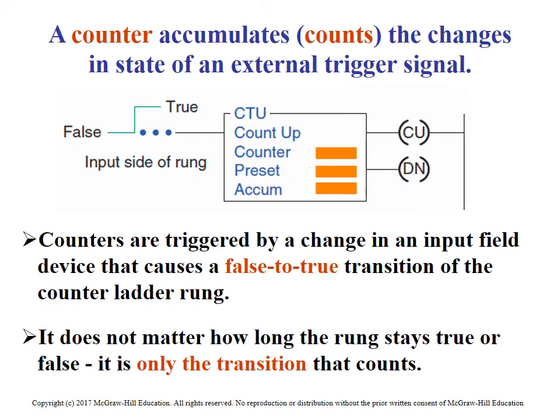As you remember in the previous segment, there are three components to the counters: there's the address, the preset value, and the cumulative value. It consumes three words — the control word, which has bits associated to it such as counter up, counter down, done bit, and all those. And then the preset word and accumulated word.